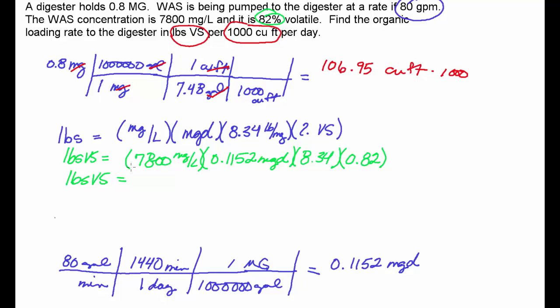How many pounds of volatiles have we got going here? I've got 7,800 times 0.1152 times 8.34 times 0.82. So I've got 6,145. So that's how many pounds of volatiles are going in there every day.